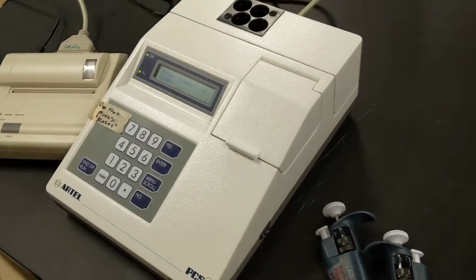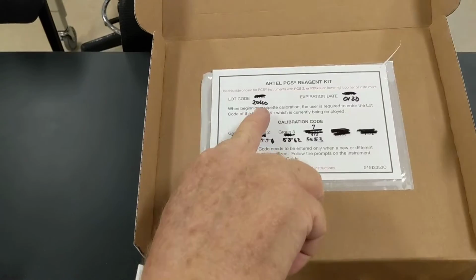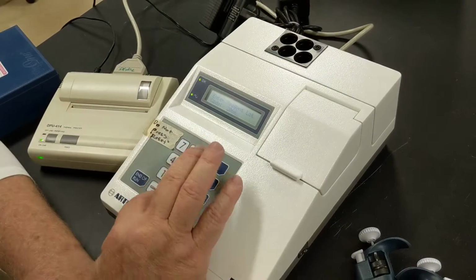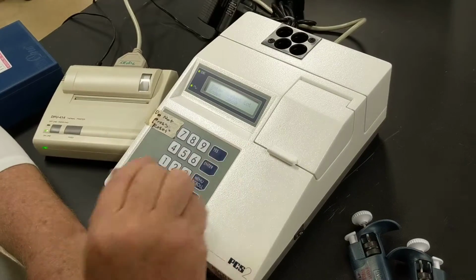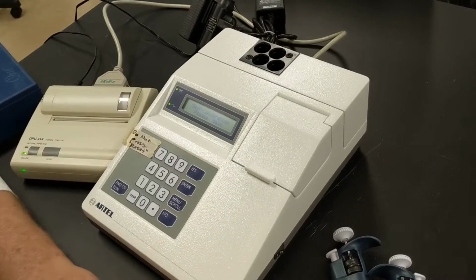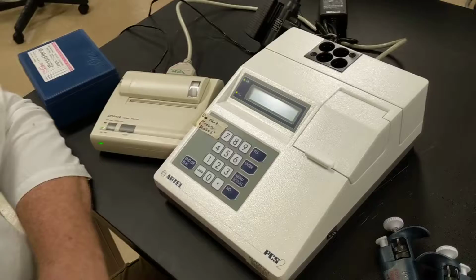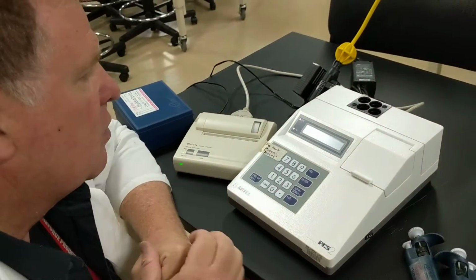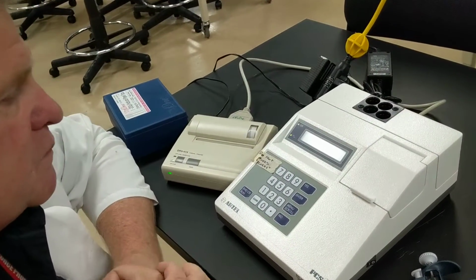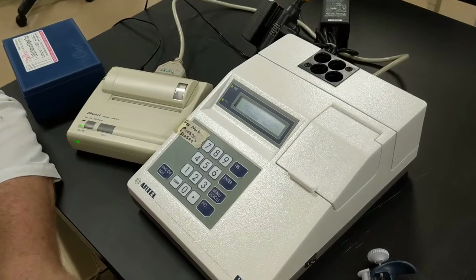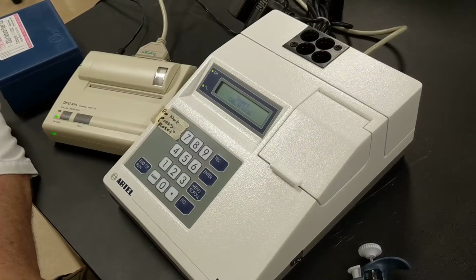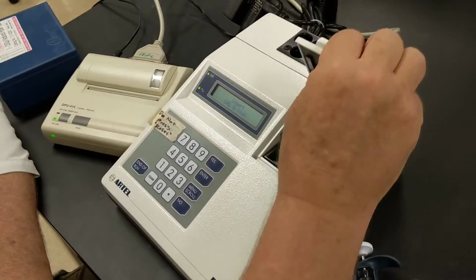We're going to enter the lot code. So the lot code from this box is 20660, 20660, and hit enter. It will then do a self-calibration test. We need to wait a little while, but it doesn't take too long. All right, we see here a little bit of noise on it, and so it's done. So what we're going to do is insert vial A. So here we have our vial.